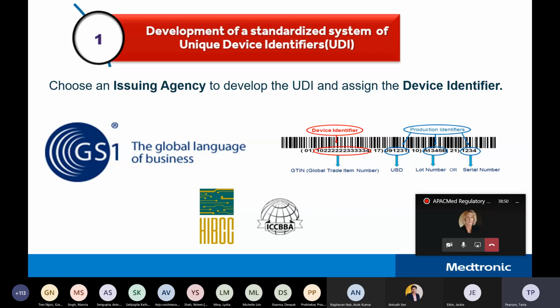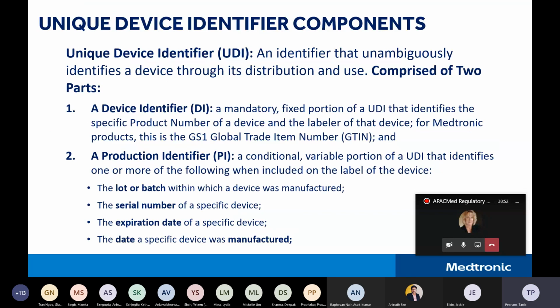And so there are two components of the UDI. There is the device identifier, and there is the production identifier. The device identifier is a fixed portion that identifies a specific product number of the device and the label of the device. For Medtronic, this is going to be the GS1 Global Trade Item Number, which is the GTIN. So it's going to be the first part of the UDI.